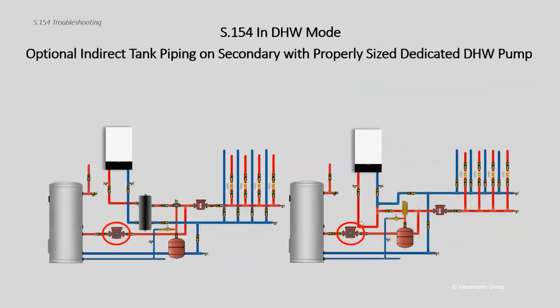The other option — if you're not sure about the pressure drop in the tank — the boilers all come with relay outputs for these domestic hot water pumps. You can cap those domestic hot water connections and connect that indirect tank on the secondary side. In programming during commissioning, you tell the boiler this, and it doesn't exercise the diverting valve anymore. The boiler only has to worry about flow through the primary loop. That dedicated domestic hot water pump is responsible for overcoming the pressure drop in that specific tank. A couple of options if you have a really high pressure drop — not a bad idea to put the tank on the secondary side.